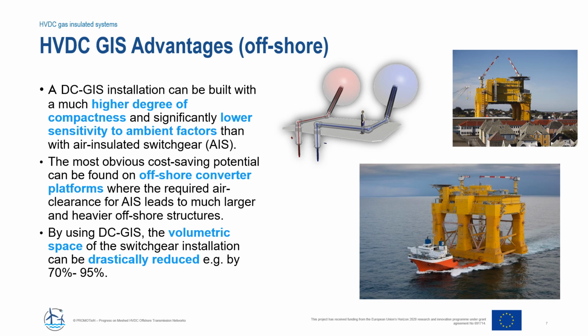But until now, again, there has been only a little operating experience. Users intended to employ gas-insulated HVDC systems expect high reliability and long-term performance. This leads to the need for long-term tests on gas-insulated HVDC systems in general. And the Work Package 15 has been formed to make a substantial contribution to increase the technology readiness level of gas-insulated HVDC systems.